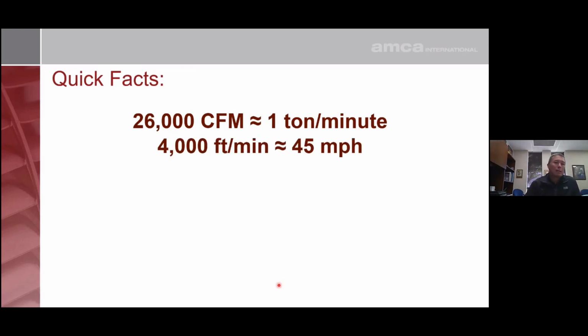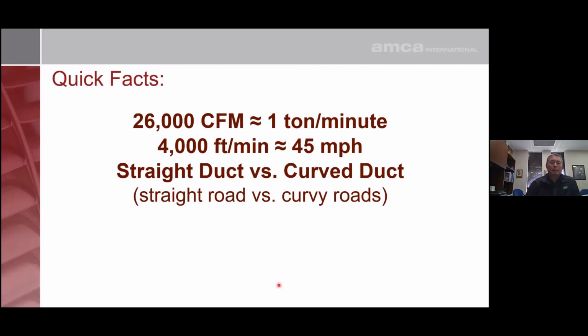4,000 feet per minute velocity is the minimum conveying velocity for most materials. Like if you have a dust handling system, moving sawdust or other fines through the fan, you typically want to run the air through the system at 4,000 feet per minute. You're moving air through the fan at roughly 45 miles per hour. So, if you have a pickup truck or a car driving on a straight road, you typically get there much more efficiently, much quicker, and with much less energy cost than if you pick a curvy road, especially one with abrupt 90-degree turns and stoplights.